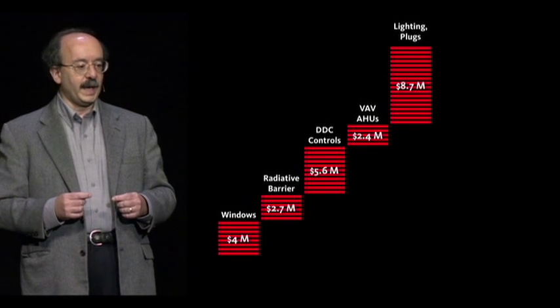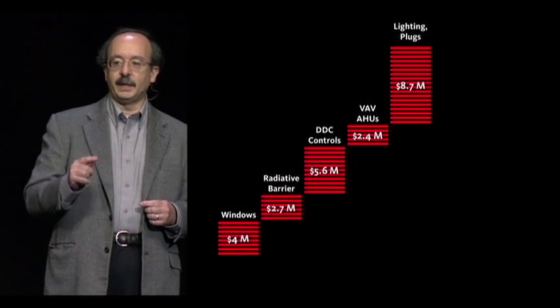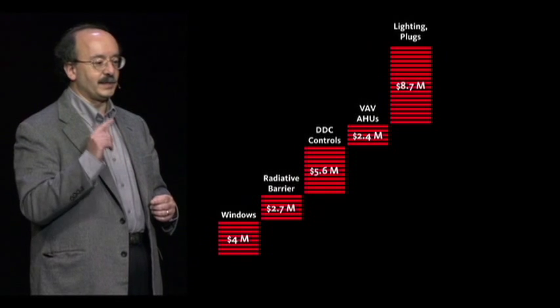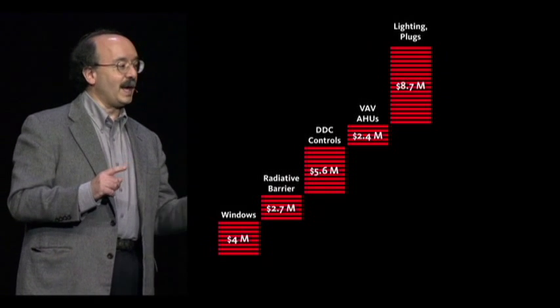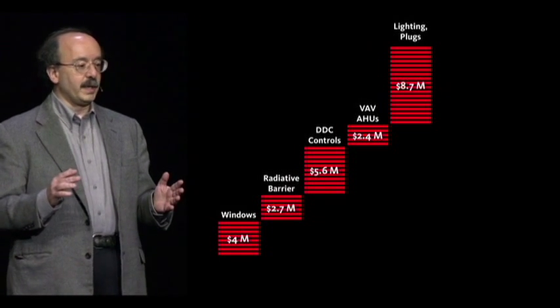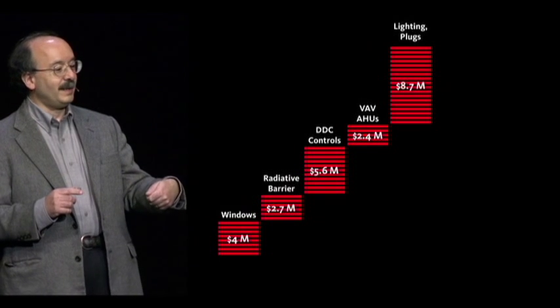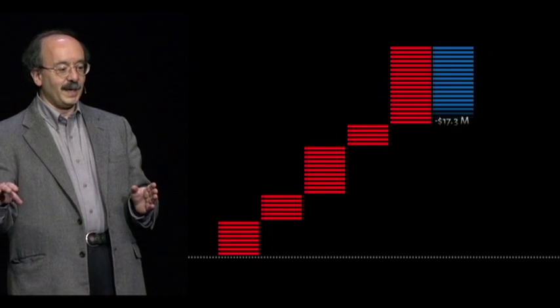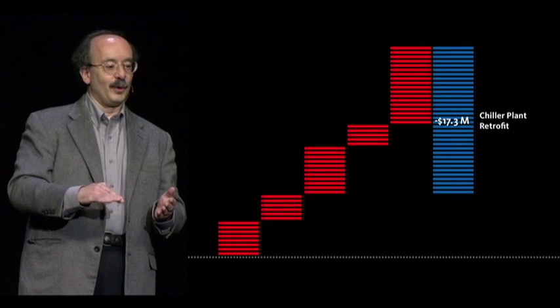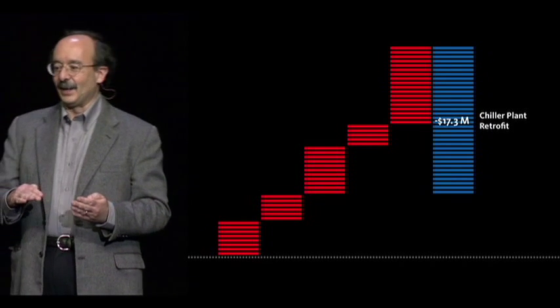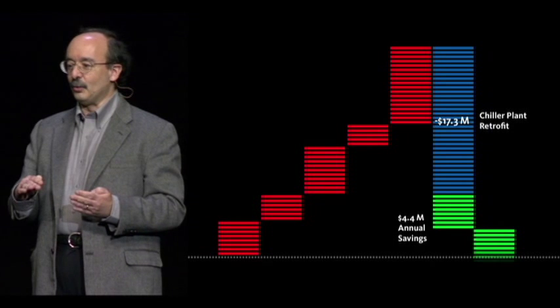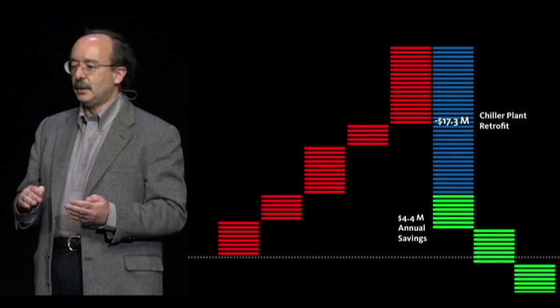That cuts their winter heat loss by at least two-thirds and their summer heat gain by half. That plus better lights and office equipment cuts the peak cooling load by a third, and that lets us tunnel through the cost barrier, because now the old chillers no longer need to be replaced and expanded. Instead, they can be renovated and reduced, saving $17.3 million in capex, which helps pay for all the other improvements.